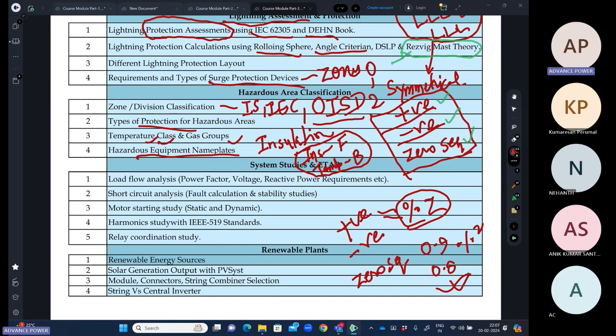Then we'll come to the system study. Theoretically, everything will be covered before, and the thing which we will practice is in ETAP. So we'll start with the load flow studies. In load flow studies, we'll discuss the voltage at different nodes. We'll prepare a complete SLD of any either oil and gas system or renewable system. We'll check the power factor. We'll check the voltage at different voltage levels. What is the voltage drop that is happening? What is the reactive power requirement, or is it consuming, or is it supplying.